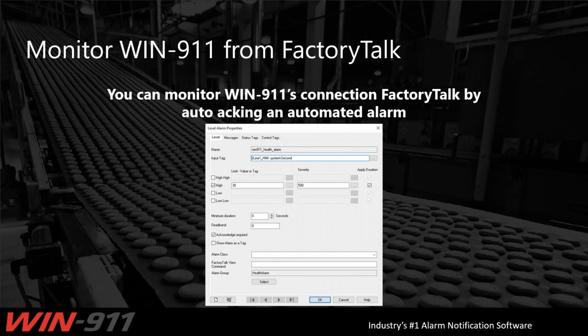And you could write a script in FactoryTalk to check to see if the alarm remains unacknowledged for a certain amount of time, because this is all running on an interval. And if it were, then you could take some action within FactoryTalk. I don't have an example script for you guys today, but that's something I'll work on and get published on our knowledge base. Something I've been meaning to do anyway, so I will take that action item on for you guys and get that posted sometime after this webinar. Again, you'd want to filter this health alarm from your alarm summary, because it's going to come in and out and would be distracting to anybody watching the alarm summary.